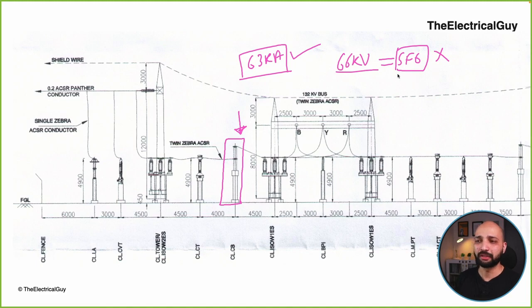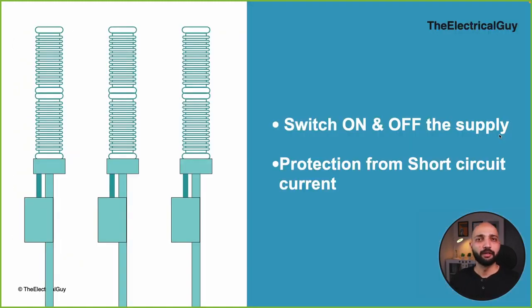So SF6 circuit breaker is used from 66 kV and above voltage level up to 800 kV, and below 66 kV vacuum is preferred. So the function of circuit breaker in the substation is to switch on and off the supply, of course normal and also abnormal, and it also protects from the short circuit current, huge short circuit current. Clear?